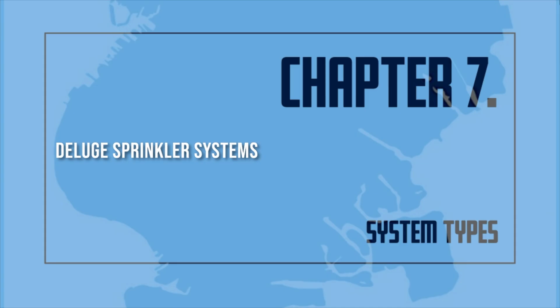The sprinkler heads in the deluge system are open at all times. Under normal conditions, there is no water in the piping. The air in the piping is not under pressure. A closed control valve prevents water from flowing into the system. A fire detection device automatically opens the control valve when a fire is identified. A supervisory device signals when the valve is opened. When the valve is opened, water flows into the system. The water is then discharged out all of the sprinkler heads. The water control valve may also be opened manually.